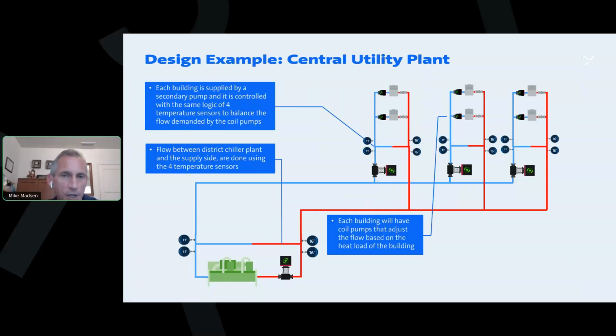You want to do it as quick as you can, but you're going to leave your control valve in. You're going to put your pumps in, your check valves. You're going to leave your control valve in so that we're not pushing water through an air handler when we don't want to. And then once all your buildings are converted, we'll completely open that control valve or completely remove that control valve. So in that case, you're not going to get all these tremendous energy savings until the job is done, but it is an approach we can use in a campus type application.